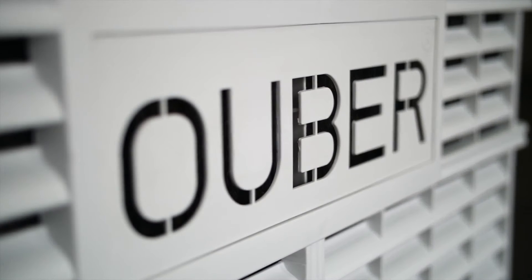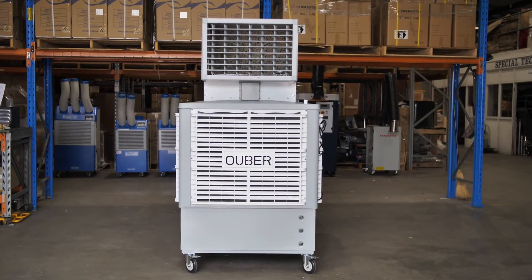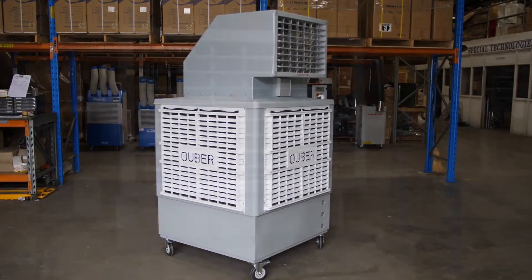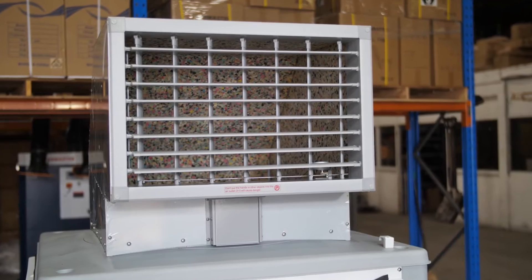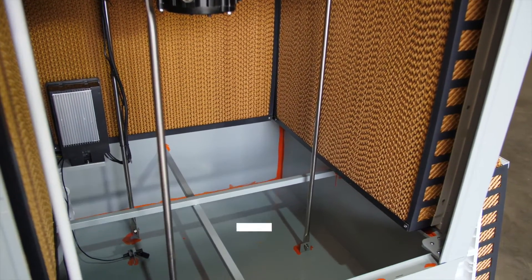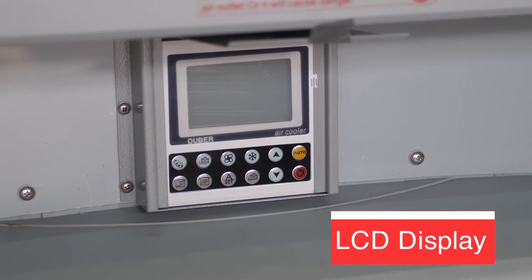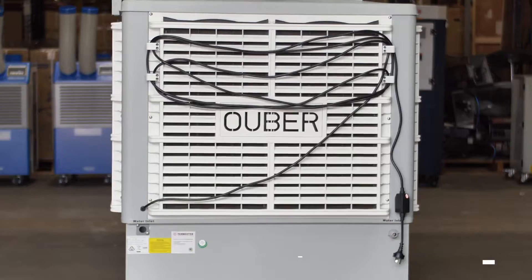Ouber industrial evaporative air coolers utilize the natural process of evaporation to cool the air. Our coolers use a low wattage water pump to circulate water from the water tank onto the cooling pads. The fan draws air from outside the unit through the wet pads, and as it passes through the pads, the air is cooled by evaporation.